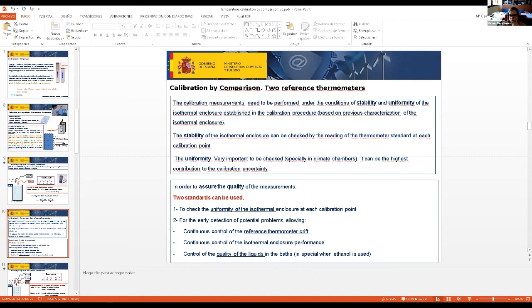Also, the isothermal enclosure drifts, and with two thermometers, you can check this drift. This drift is not very usual, but if you use the isothermal enclosures a lot, in the end they will drift, and you need to have this under control. Another point is that when you work with baths and isothermal enclosures, the quality of the liquids changes with use, with the number of uses and with time.